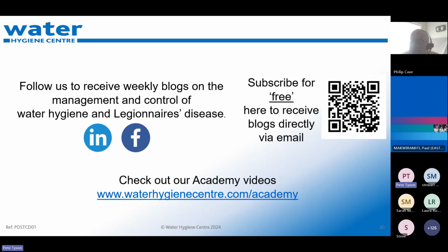They have to be serviced according to the manufacturer's guidelines, often every 12 months - stripped down, disinfected, descaled, and put back together. During that time you also do the fail-safe check to make sure it's working accurately. From a replacement perspective, I'd go with whatever the service provider suggests once they're perished in any way, shape or form.